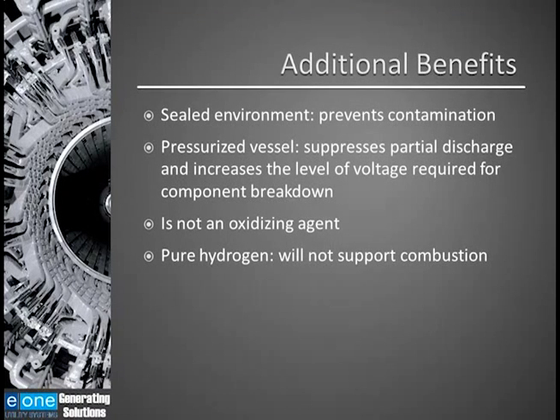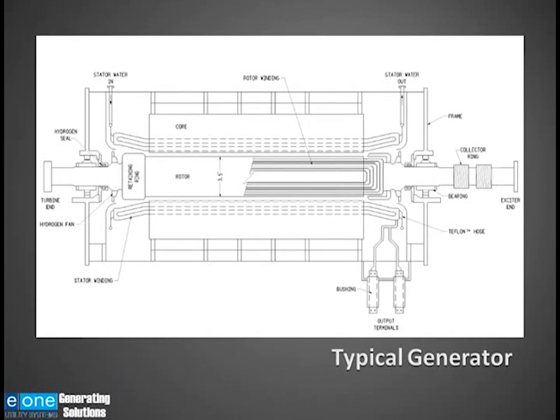There are additional benefits in using hydrogen as a cooling gas. Because it's a sealed environment, the generator has less chance of contaminants entering into it, such as water, dirt, or sand. Because it's a pressurized vessel, it suppresses partial discharge and also increases the level of voltage required to break down components. Hydrogen is not an oxidizing agent like oxygen is, and pure hydrogen will not support combustion. One of the problems with using hydrogen is you have to keep it in the generator case, and because hydrogen molecules are so small, they are hard to contain.